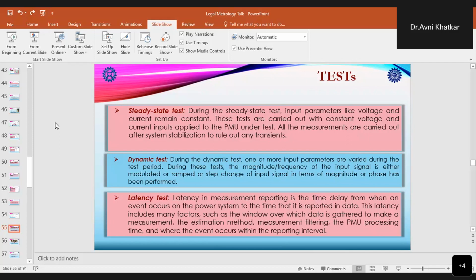Whereas in the dynamic test, one or more input parameters are varied during the test period, and in this test, the magnitude or frequency of the input signal is either modulated or ramped, or a step change of the input signal is performed in terms of magnitude or phase.